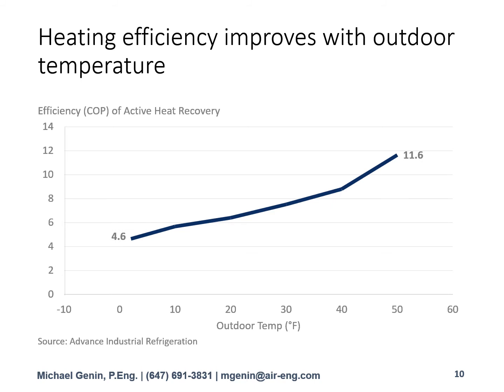And what that results in is average seasonal efficiency. In a Toronto or northern climate, the seasonal efficiency ends up being at a COP of 7. Again, this is a huge improvement over air source heat pumps, and a huge improvement in operating costs when compared to gas heat as well. So how do the operating costs pan out over a whole given heating season?